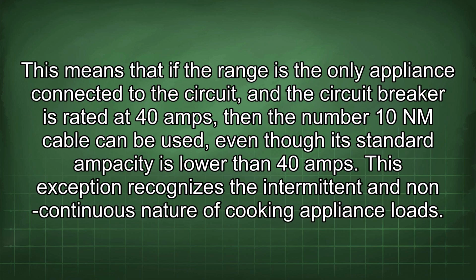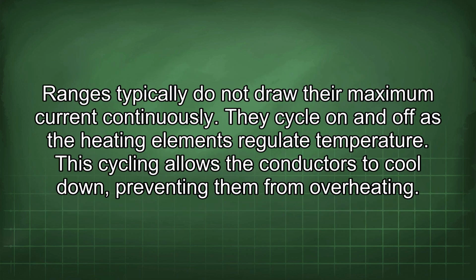This means that if the range is the only appliance connected to the circuit, and the circuit breaker is rated at 40 amps, then the number 10 NM cable can be used, even though its standard ampacity is lower than 40 amps. This exception recognizes the intermittent and non-continuous nature of cooking appliance loads. Ranges typically do not draw their maximum current continuously. They cycle on and off as the heating elements regulate temperature. This cycling allows the conductors to cool down, preventing them from overheating.